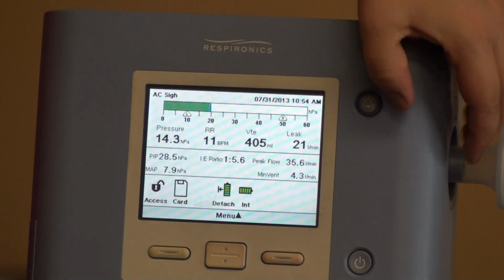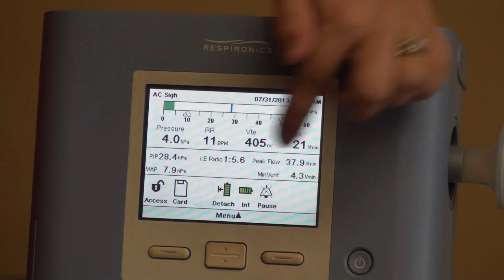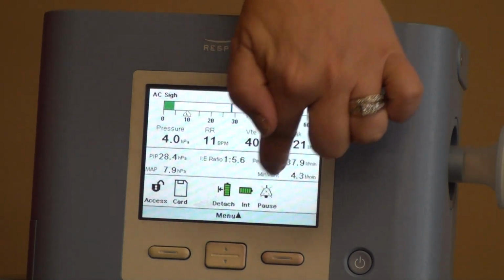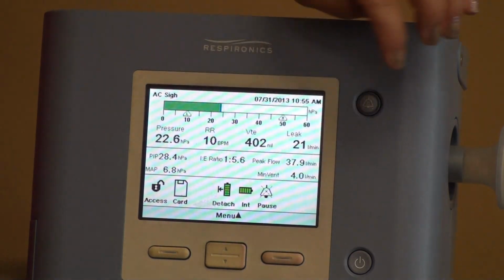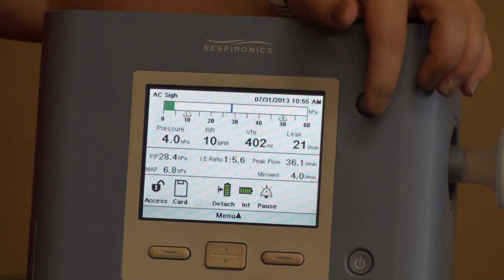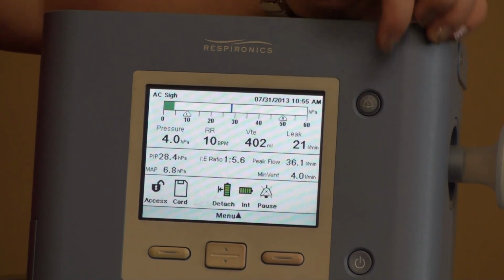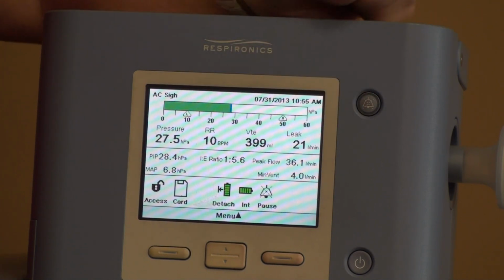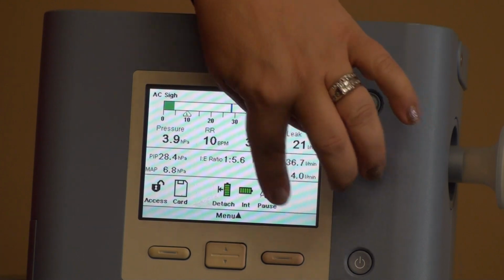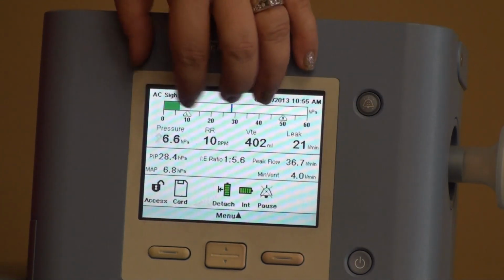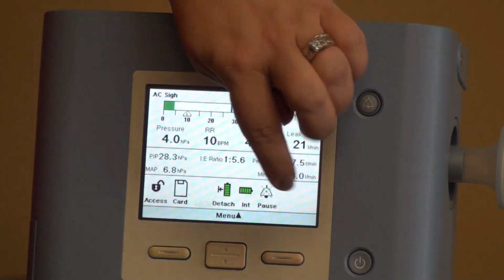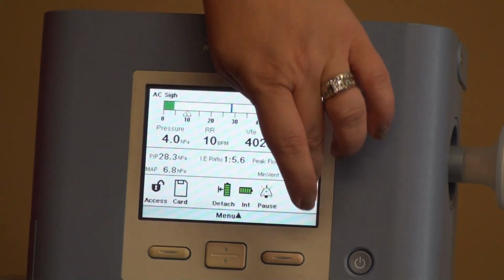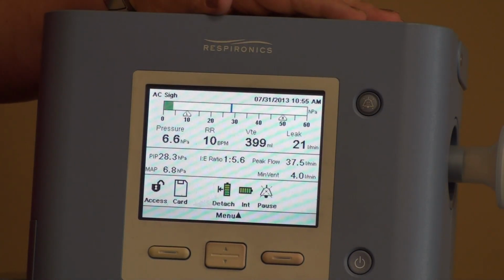The next one over is if I hit my pause right here, you can see that a bell comes up with an X across it. That means my alarms are paused at this point. Okay, so they'll stay that way for 60 seconds. The next one, if you have a ramp breath in certain types of modes that we have in here, you might have a different type of breath. You might see a little ramp here, and that's just a type of breath. You don't have to worry about it or do anything with it. It's just the type of breath that will happen.